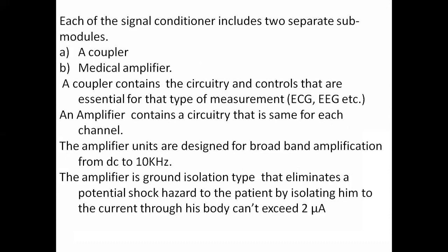If there are any disconnections in the leads or in the circuitry, that may lead to a shock. To avoid such situations, this driver amplifier or amplifier section will have an isolation, which eliminates any shock to the patient while measuring. So that will be avoided.